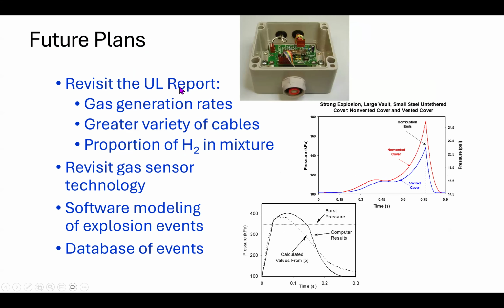Okay. Revisiting the UL report. The UL report, remember I mentioned that UL defined the mixture, typical mixture in a manhole, mixture of gases. Now, that's not always true for every single situation. Okay, so computational methods allowed variation of concentration of gases or amount of gas and come up with some sort of guidelines. Proportion of H2 in the mixture is also very important because hydrogen is very light. It would settle close to the top of the manhole and burn very quickly. Okay, so that was not included on most of the tests because just two totally different timelines of the event.